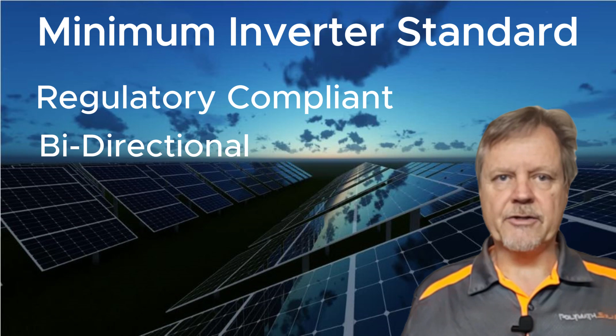If you want your inverter to really render decent savings, it must be able to feed in and have feed-in control. Most municipalities and estates don't yet allow feed-in to the network, so you need some other way to control that feed-in up to a certain point. Typically the inverter will have a current transformer, or CT.